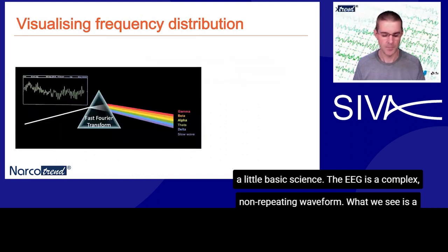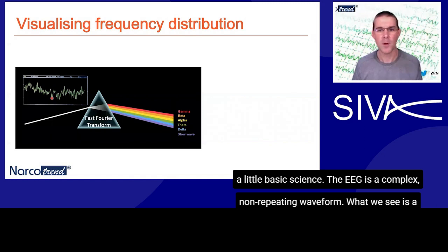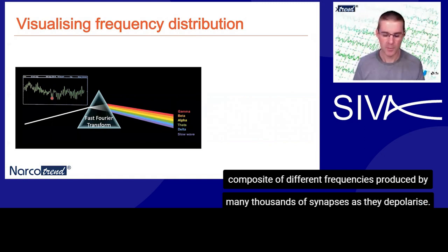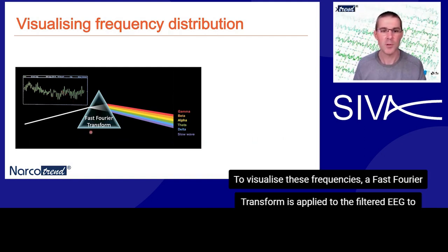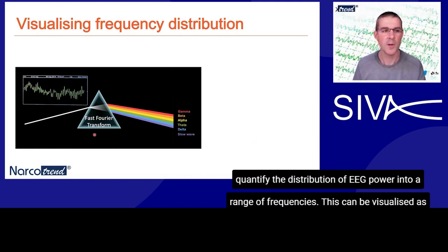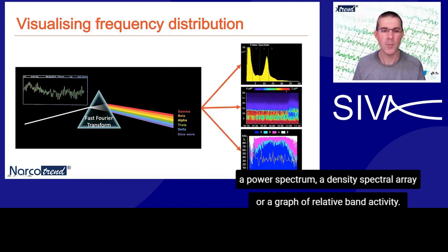A little basic science. The EEG is a complex, non-repeating waveform. What we see is a composite of different frequencies produced by many thousands of synapses as they depolarise. To visualise these frequencies, a fast Fourier transform is applied to the filtered EEG to quantify the distribution of EEG power into a range of frequencies. This can be visualised as a power spectrum, a density spectral array, or a graph of relative band activity.